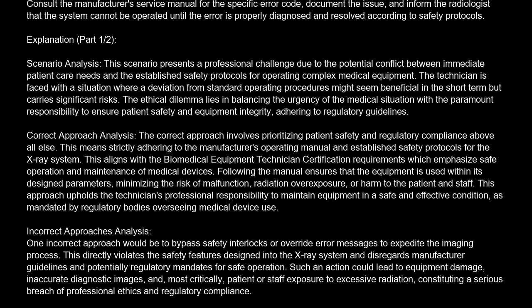The correct answer is C. Consult the manufacturer's service manual for the specific error code, document the issue, and inform the radiologist that the system cannot be operated until the error is properly diagnosed and resolved according to safety protocols.